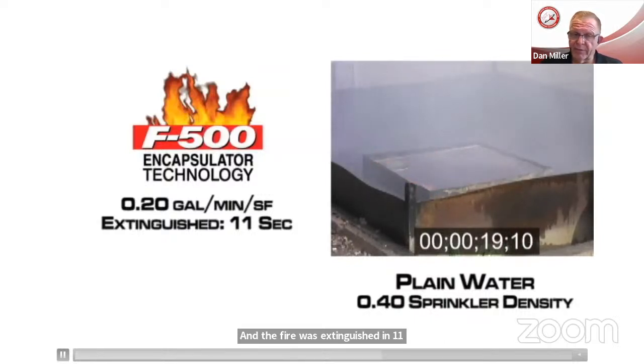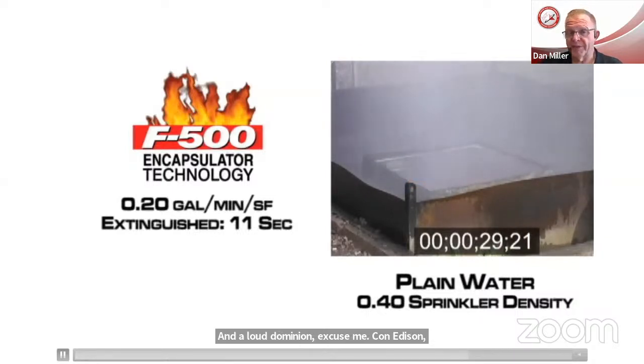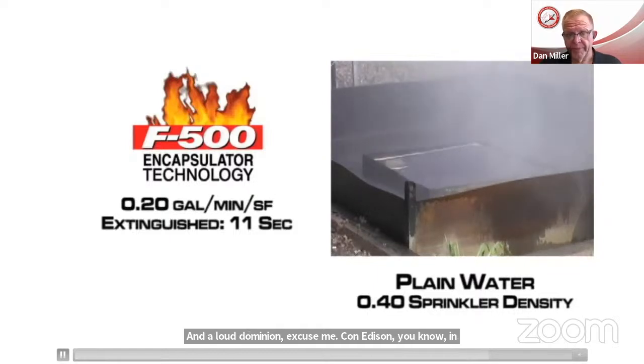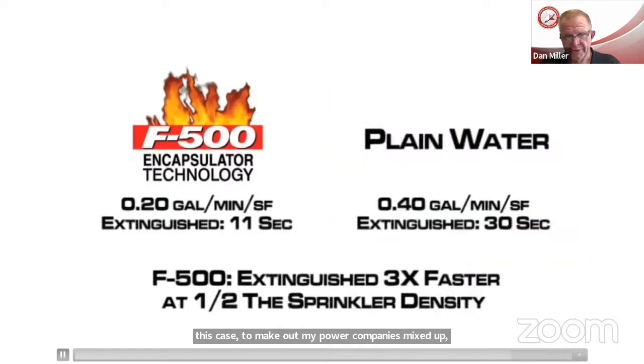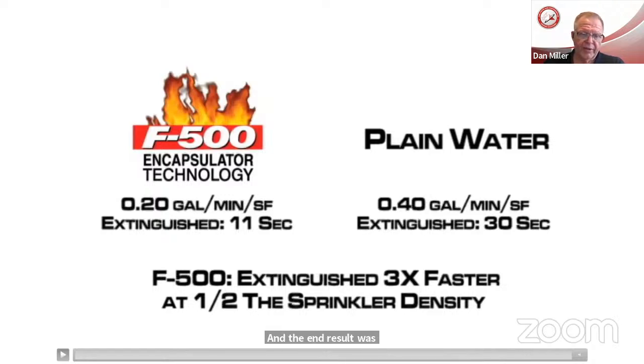Now, this was considered a full-scale test. It allowed Dominion, or excuse me, Con Edison, no, Dominion in this case, excuse me, got my power companies mixed up. Dominion to keep their existing sprinkler system, to not have to put millions of dollars into it. And because they were able to do that and incorporate or proportion F500 into that sprinkler system, they were able to save a lot of money, put fires out quickly. And the end result was that with F500, the fire was extinguished 3 times faster at half the sprinkler density of plain water.